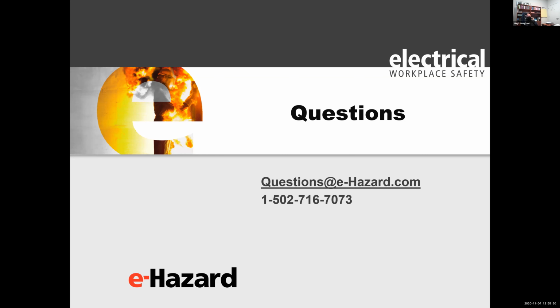I encourage you to use the NFPA 70E standard. If you can use the tables, label with the tables. Many small companies like a warehouse, we have a laboratory here in Kentucky. We've got a 5,000 square foot building. We've done an arc flash study on our electrical panels. And they are slightly more because they're three-phase panels than what the 70E standard would say. So we have made sure that we have our things labeled. But if we had just followed the 70E standard, more than likely we would have done fairly well. But our transformers were a little bigger than normal.